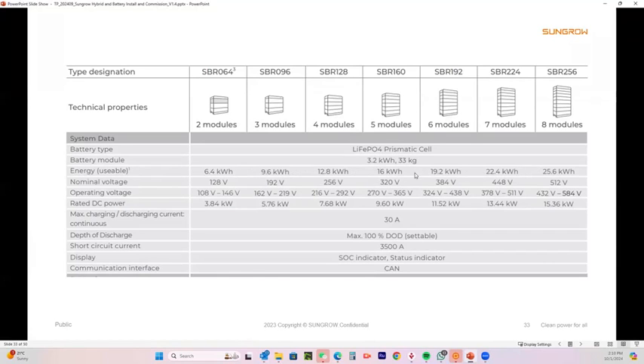And obviously you need to make sure that you're going to actually charge that capacity every day. Also take note of the voltage, okay? These are series connections, and the inverters, each inverter, if you look at the data sheet, it will tell you the maximum battery voltage input. So you cross-reference this stuff here. Now, I happen to know that the maximum battery voltage input on a single phase hybrid is about 500 volts. So with 6 modules, the maximum there is 438, that's fine. But if I put 7 modules on, the maximum is 511 volts. So the voltage is too high, okay? So that's why I can only put 6 modules on like that.